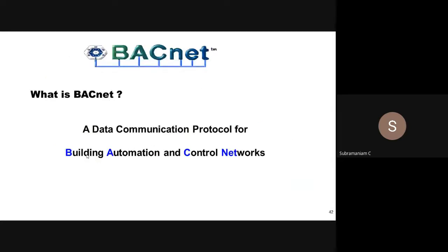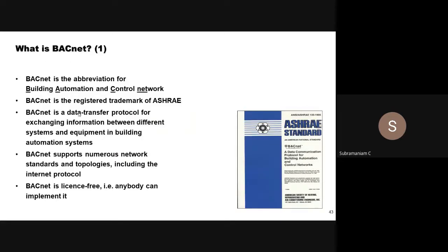What is BACnet? The ASHRAE standard is the Building Automation and Control Network standard. It is a protocol written by ASHRAE, and I think 2019 or so is the latest one. It is basically data transfer. It defines how we define an analog object and how we define a binary object. It is almost a big book of some 300, 400, 500 pages. If any manufacturer wants to start manufacturing a product, or a system designer wants to install BACnet, all that information is available in this standard.